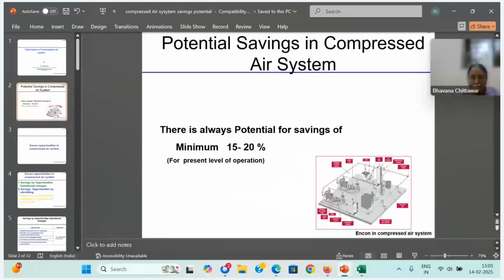There is always a minimum of 15 to 20% potential, even if it is a new installation or savings have already been achieved. It is possible either through operational changes, retrofitting, or change of equipment. When we talk about a compressor system, we should not see only the air compressor alone. We have to see it in total, starting from the compressor up to the application. In between, you have the prime mover, air dryer, filters, piping, control valves, etc.